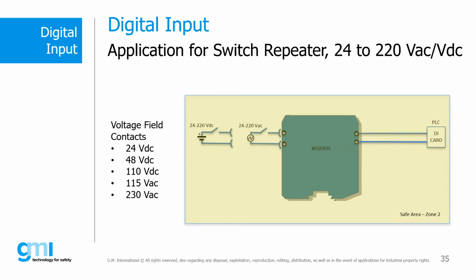But what happens if in the field we have voltage, 24 volt, 48 volt, 110 volt DC or other, and we have to signal to our system the presence or absence of this voltage? In this case, a digital input device cannot be used because its input front end is not able to accept external voltage from the field.